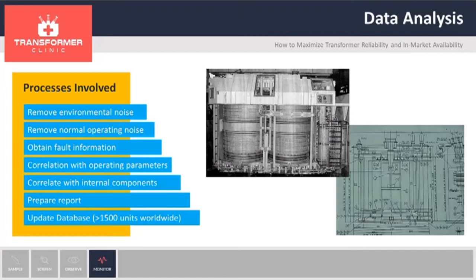Once we collect the data, we do some data analysis. The first step is to remove the noise. The noise can be environmental — wind, rain, snow — or operational, such as core noise, pump noise, or tap-changer operations. Once we remove the noise, we have the fault information. We correlate that with operating parameters, and if we have photographs or drawings, we can see what component is located in that part of the transformer and try to understand what is happening and what the acoustic emission is coming from.